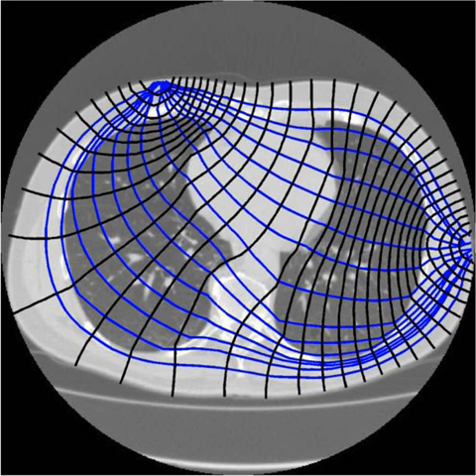This process will then be repeated for numerous different electrode configurations and finally result in a two-dimensional tomogram according to the image reconstruction algorithms incorporated. Since free ion content determines tissue and fluid conductivity, muscle and blood will conduct the applied currents better than fat, bone or lung tissue. This property can be used to reconstruct static images by morphological or absolute EIT.